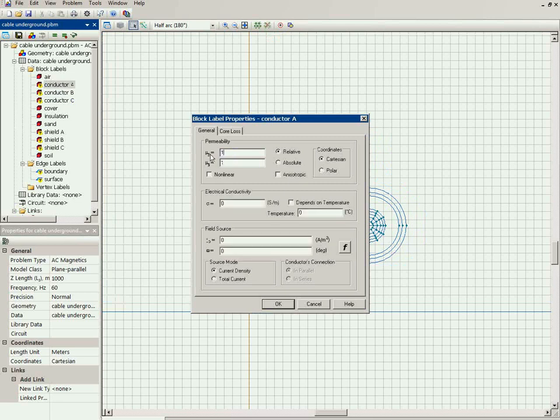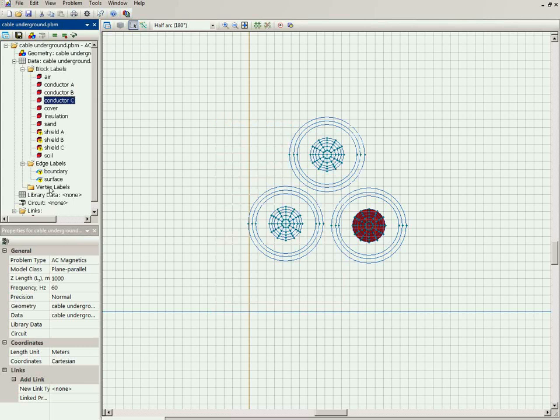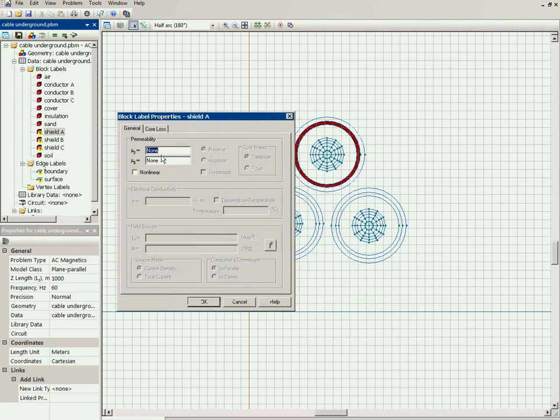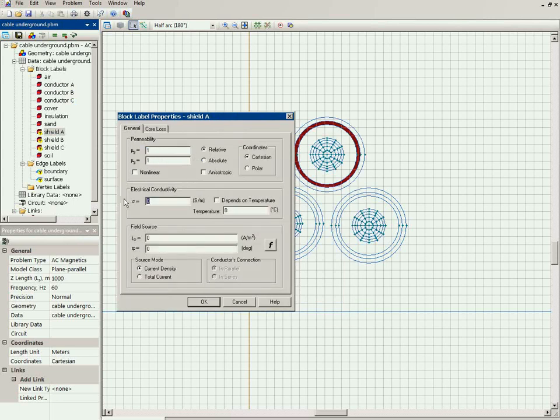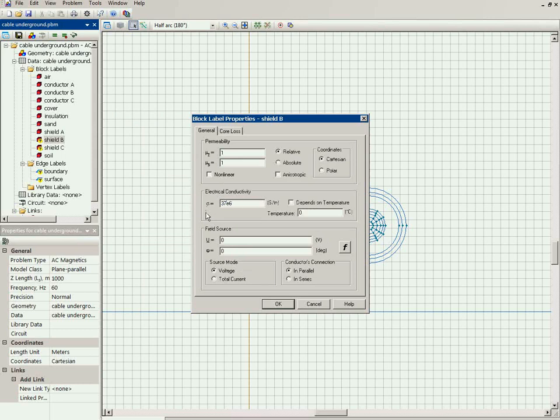Now for the conductors: the central conductor is made of copper, so the permeability is 1 and the electrical conductivity is 56×10⁶ Siemens per meter. The same values apply for the other phase conductors — magnetic permeability of 1 and conductivity of copper. The shields are made of aluminum, so the magnetic permeability of the shield is 1 and the conductivity is 37×10⁶ Siemens per meter. The same applies to the shields of the other phases.